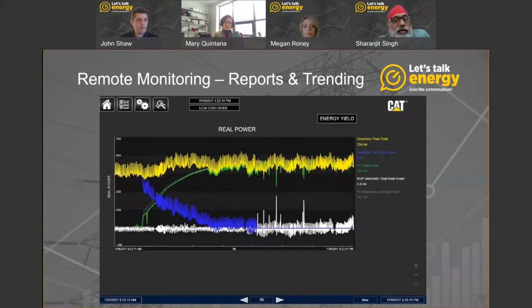Initially you can see the battery energy storage system is providing all the load, and then the genset starts running. As the sun rises, the green energy starts increasing, and the load on the generator set starts decreasing up to a point where the generator sets are shut down, and solar is providing all the energy for this particular system, and also charging up the battery energy storage system.